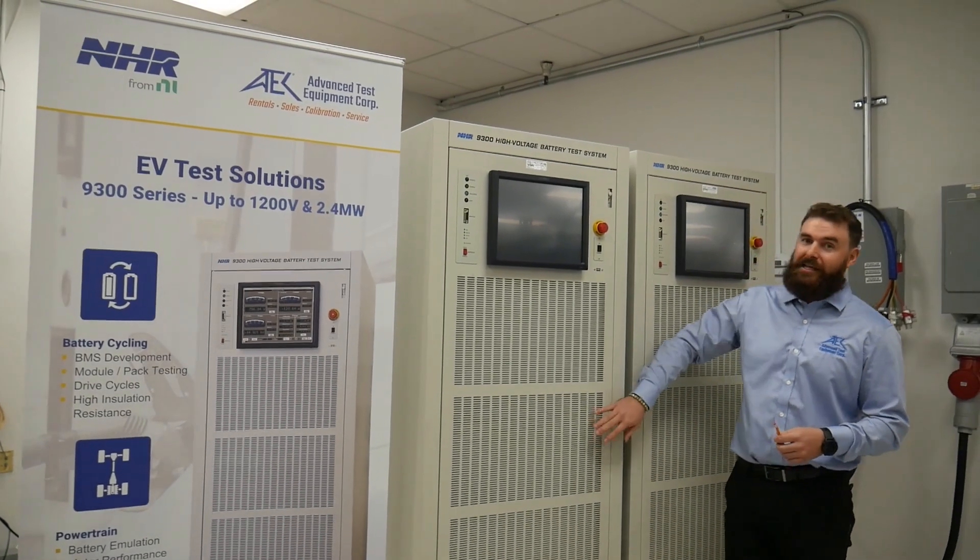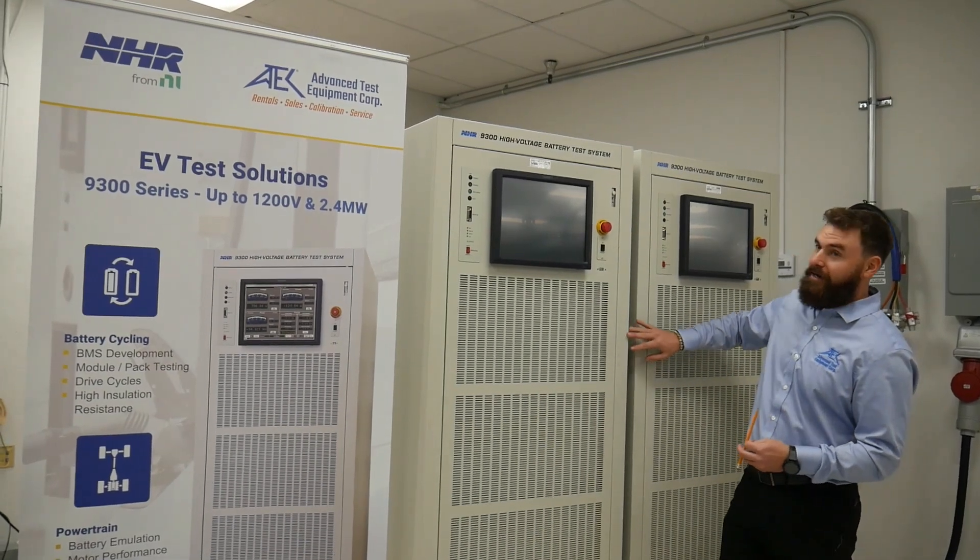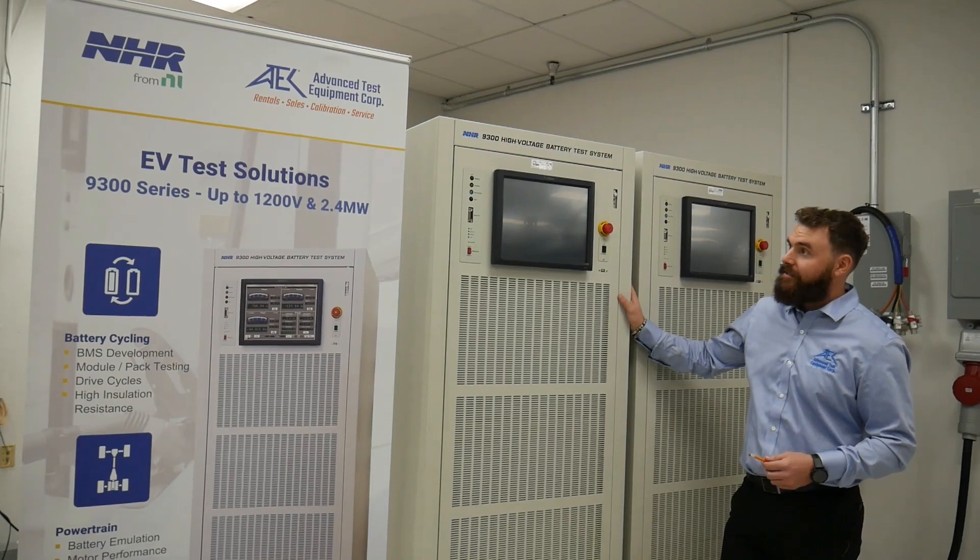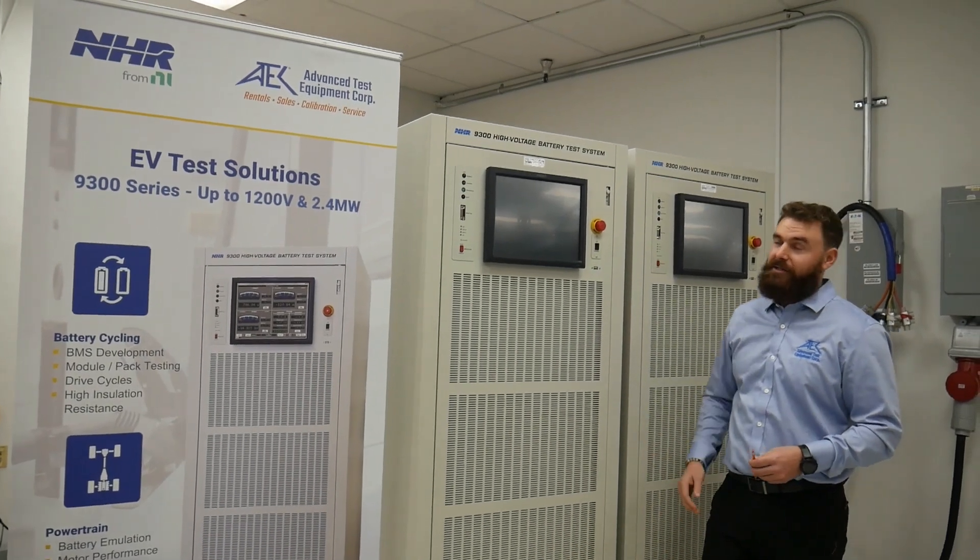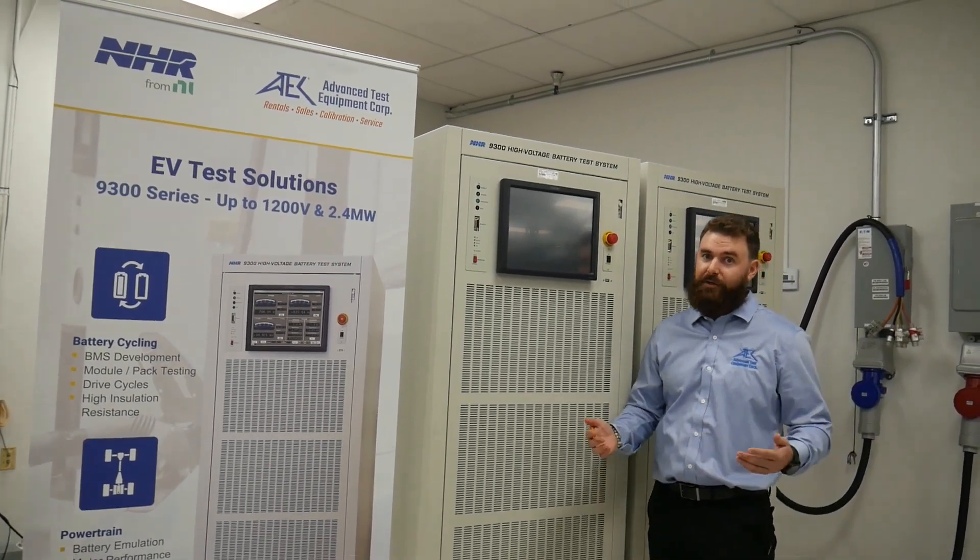Each cabinet is capable of 1,200 volts as well as 100 kilowatts. You can put them in parallel to max at 2.4 megawatts. In the video today we're going to be going over charge, discharge, battery emulation, and the software as well.